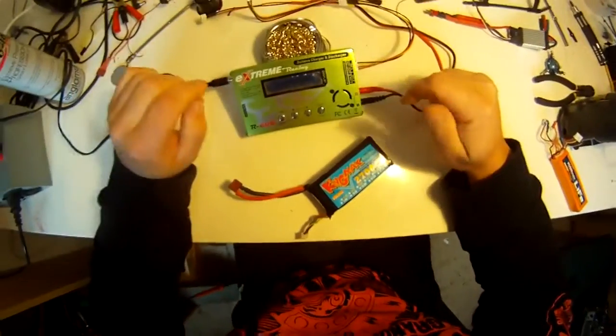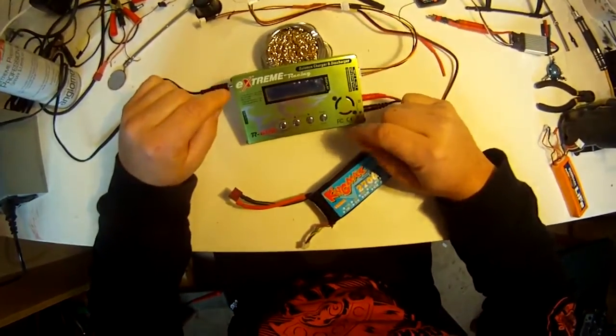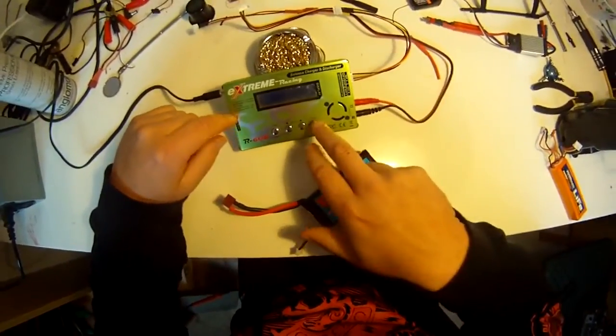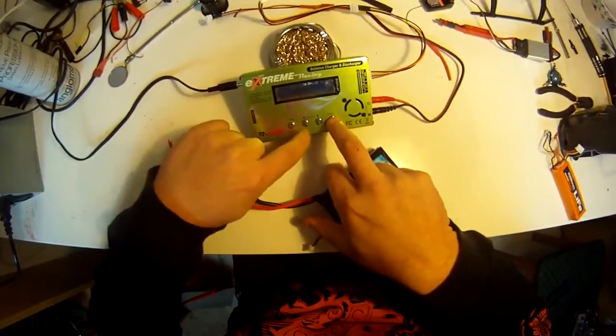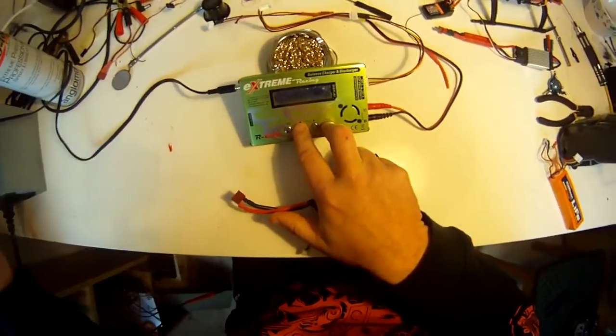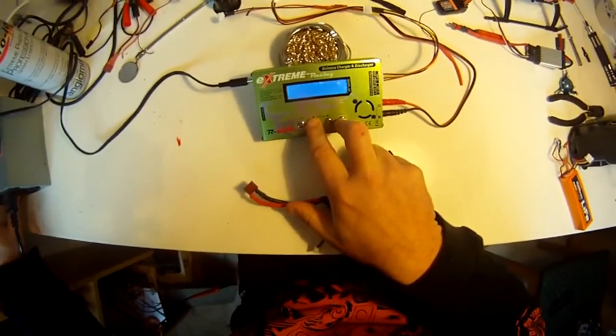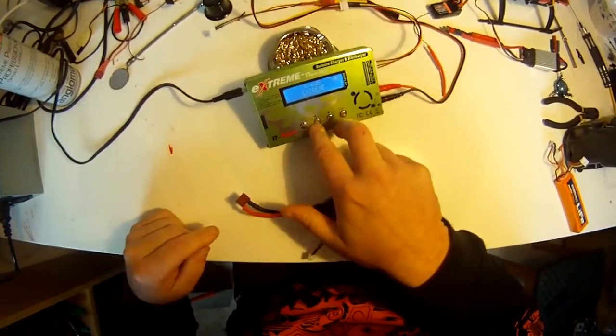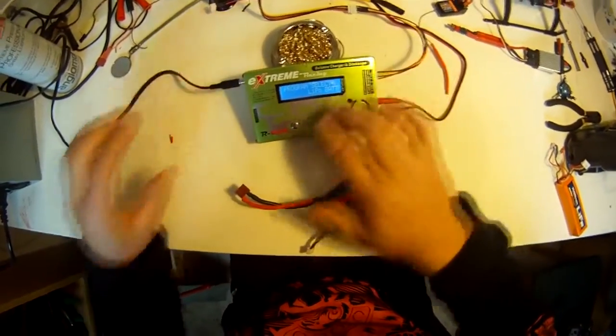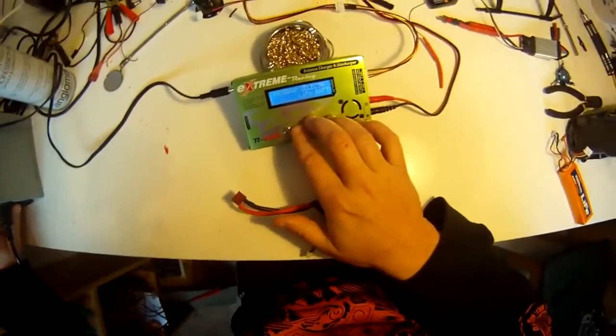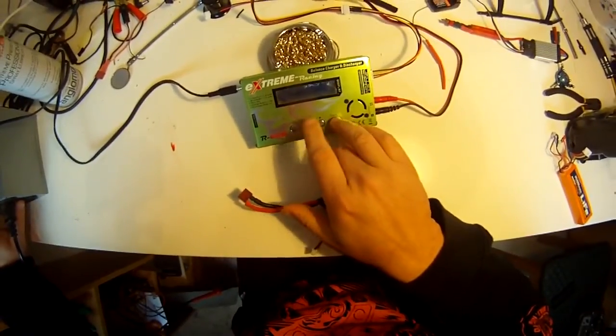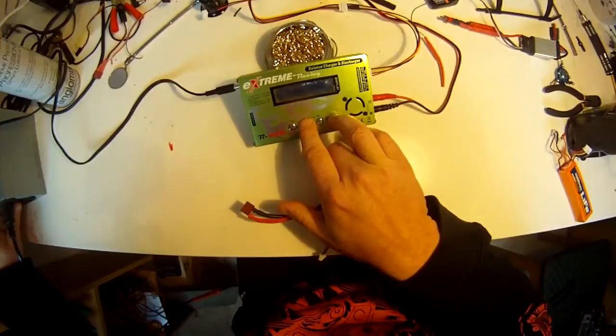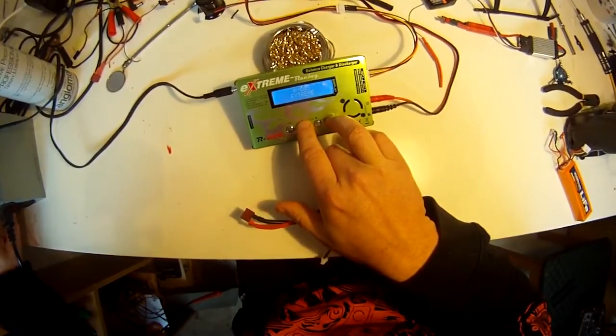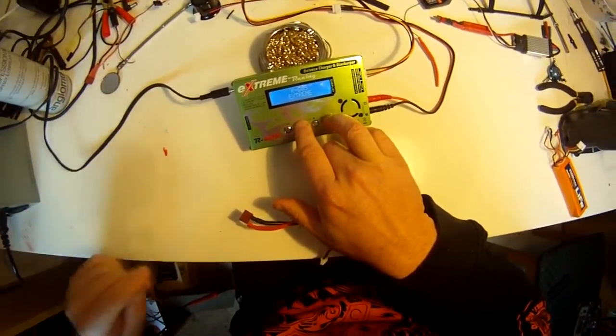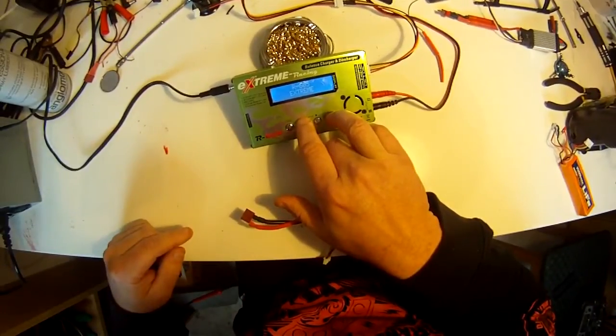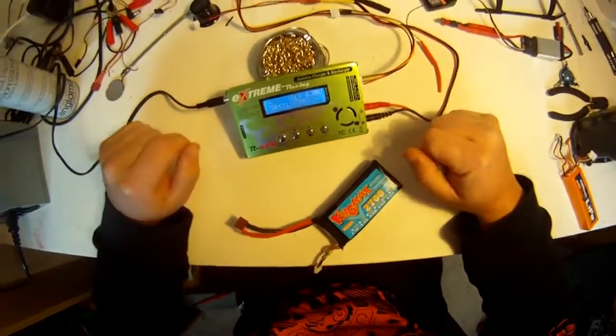Put it away. To get into calibration mode, you've got your 4 buttons across the top. Hold down start and minus, the second button, and turn it on. You'll hear it go bit-a-did. Let's try that again - hold down start and the minus button, turn it on, and just hold it down for a few seconds. And it goes into calibration mode.